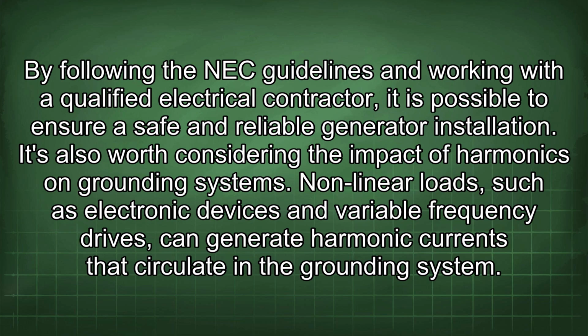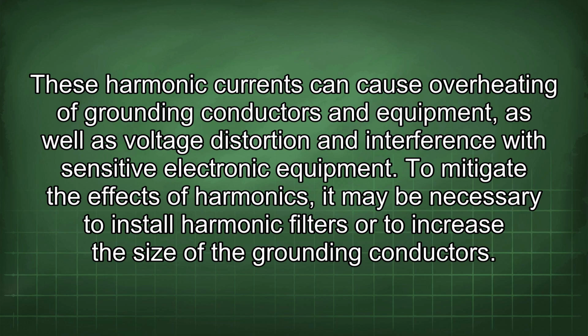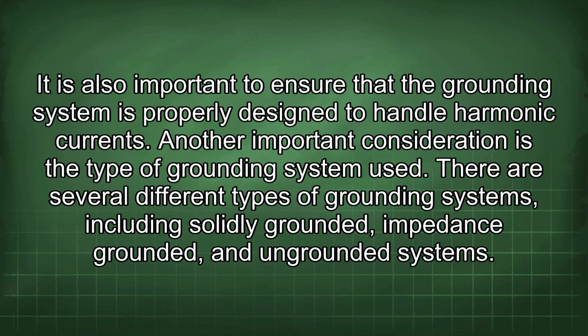reliable generator installation. It's also worth considering the impact of harmonics on grounding systems. Nonlinear loads such as electronic devices and variable frequency drives can generate harmonic currents that circulate in the grounding system. These harmonic currents can cause overheating of grounding conductors and equipment, as well as voltage distortion and interference with sensitive electronic equipment. To mitigate the effects of harmonics, it may be necessary to install harmonic filters or to increase the size of the grounding conductors. It is also important to ensure that the grounding system is properly designed to handle harmonic currents.